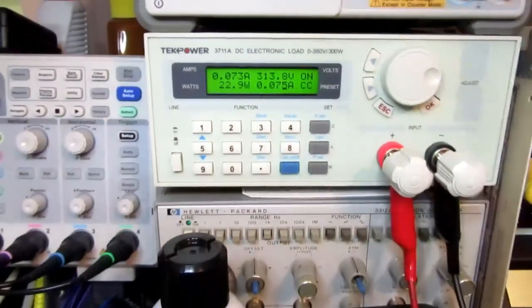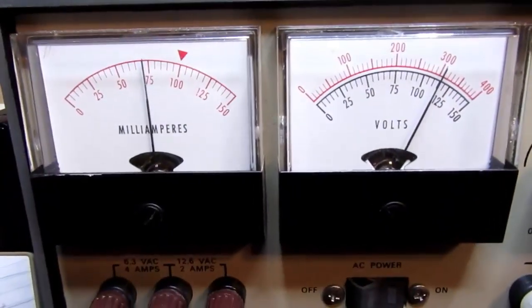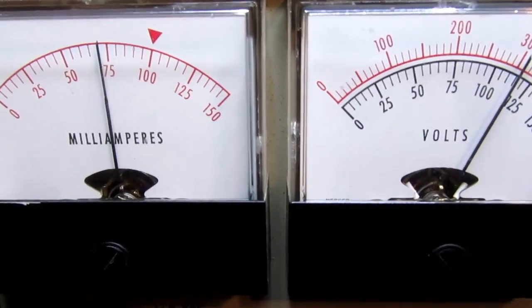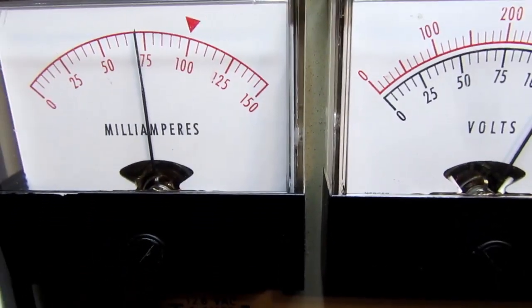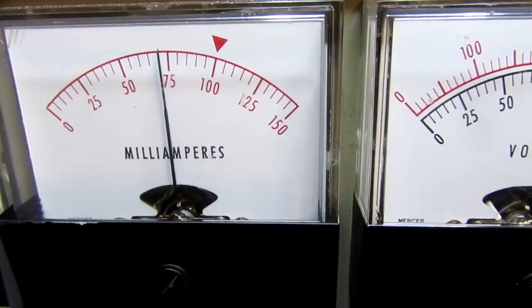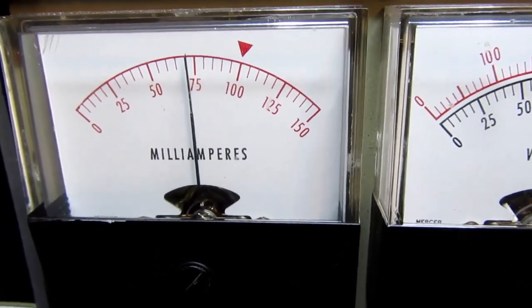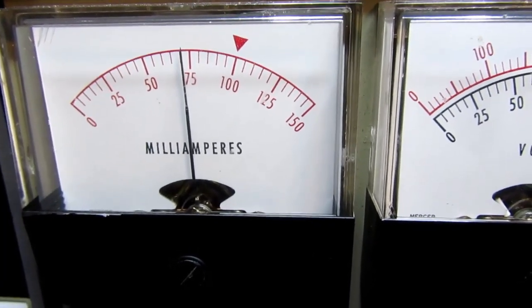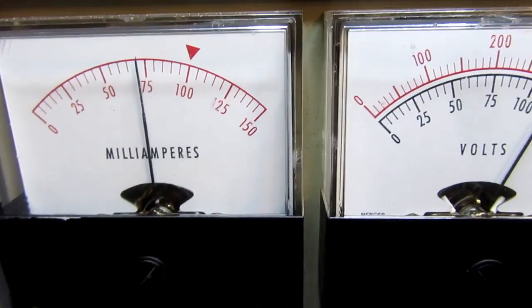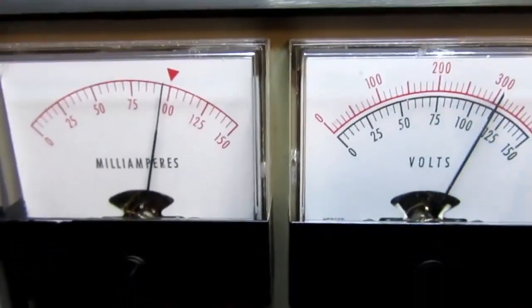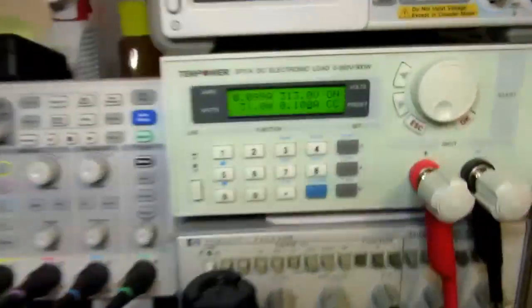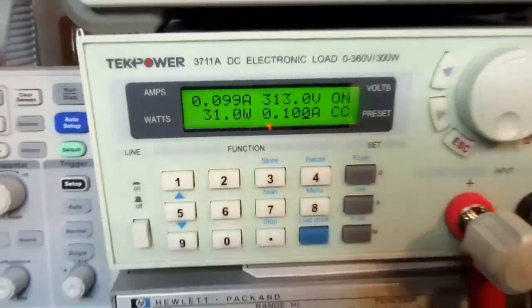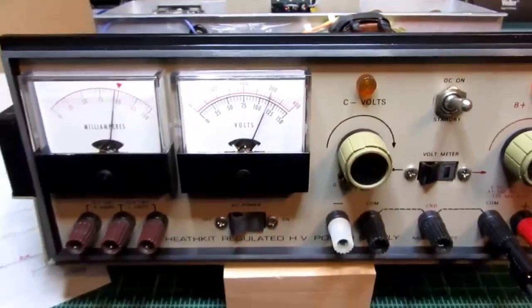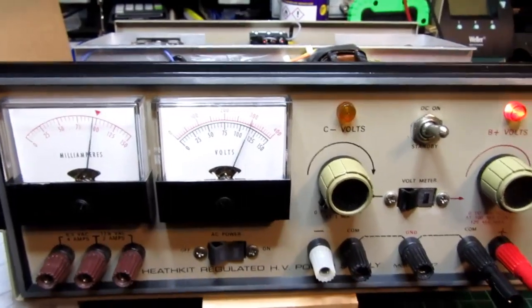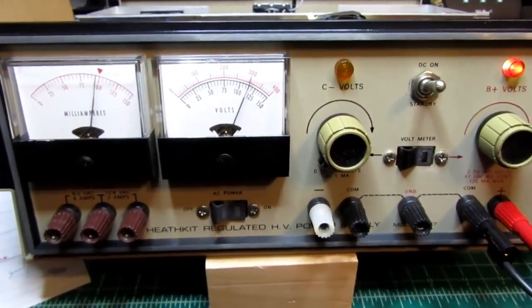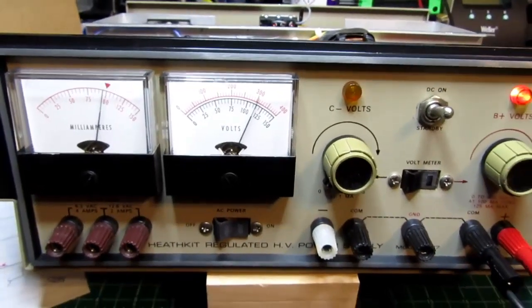Now, let's change the load. I'm going to increase the load to 70 milliamps. I'm going to crank her up to 100 milliamps. And there we go. And that's what it's doing. The voltage has not changed. So it is regulating, and it is putting out the specified amount of current without losing regulation. So that's working pretty well.